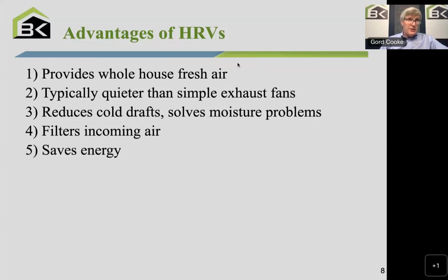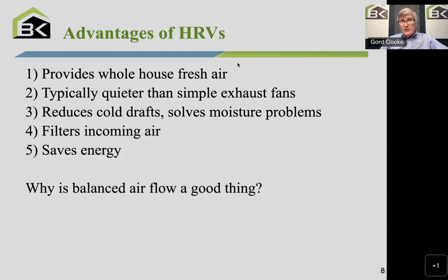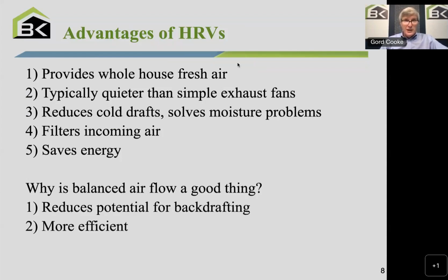And then, as I mentioned, it saves energy. It recovers roughly 80% of the temperature difference between the airstreams. So that's kind of useful. And as I say, we do want balanced airflow. That's the other nice advantage of an HRV. The 2 fans, air in equals air out, means the house is in balance, means wood stoves don't backdraft. Pretty powerful, pretty important to ensure that we have air in equals air out, especially if we're doing any wood heating or combustion, even natural gas or oil-fired furnaces typically need or want that balanced approach, and it ends up being more efficient because we're recovering 80% of the temperature difference between those airstreams.